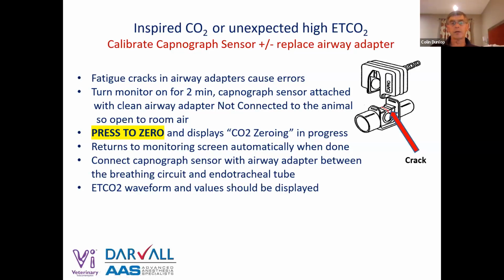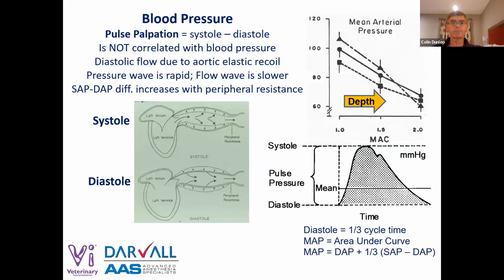So you put the capnograph on the dog and it's reading the CO2 at the start of anesthesia, 2 breaths into it, it's reading 74 with an inspired CO2 of 5 millimeters of mercury. And I would check the adapter, and I would certainly look at the patient and make sure it's breathing regularly and it's got pink mucous membranes. And then I would be looking at that adapter. And if that's not the problem, I'd calibrate the sensor. You got to calibrate the sensor, not on the patient.